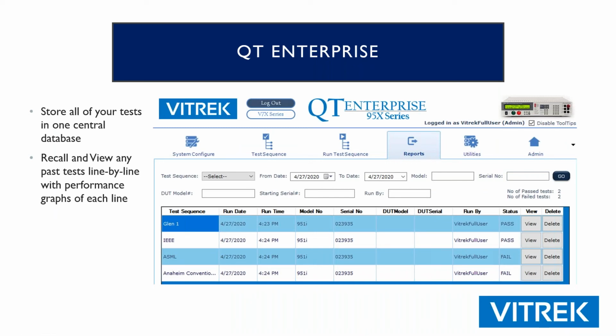All right, so this is where at the conclusion of the test, you're able to find some information. You can see when the test was run, what tester it was run on, the serial number of that, DUT model and serial number, who ran it, whether it passed or failed, and all of this information is stored. So later you can go back and look at your throughput by user, by tester. You can find out that certain DUTs have higher or lower pass rates than other DUTs, and really analyze all of this for quality and performance.